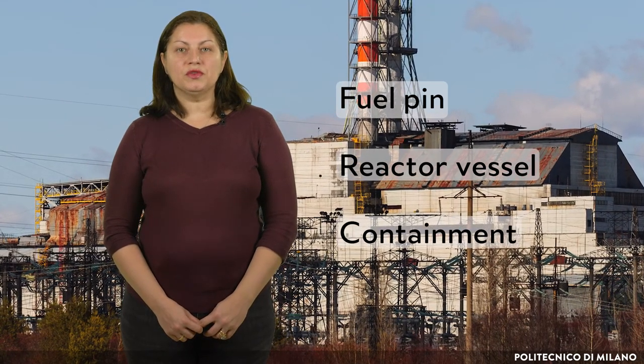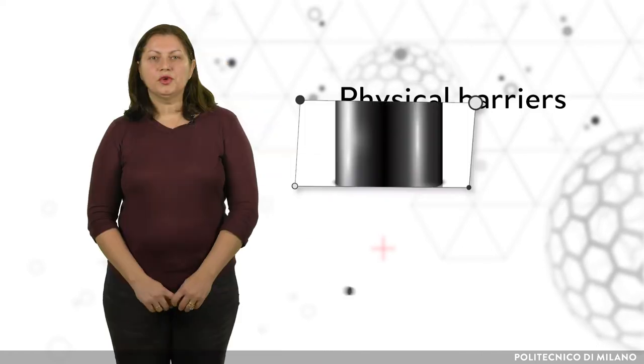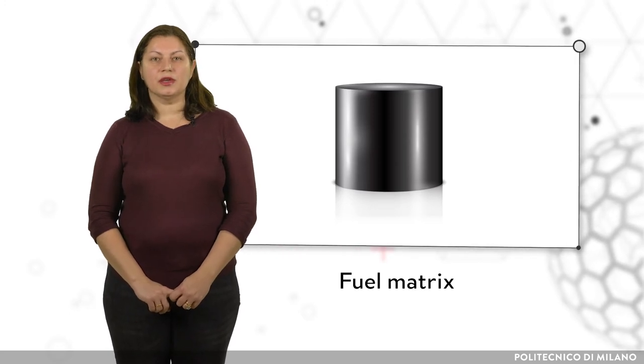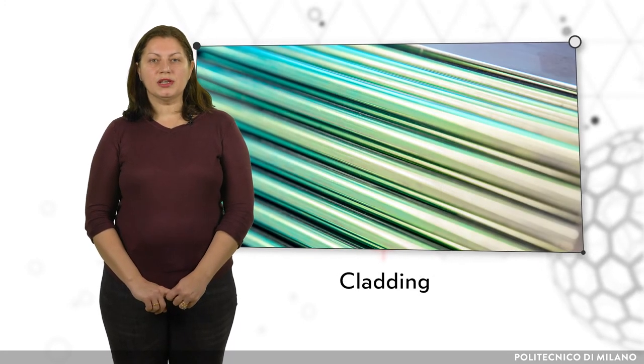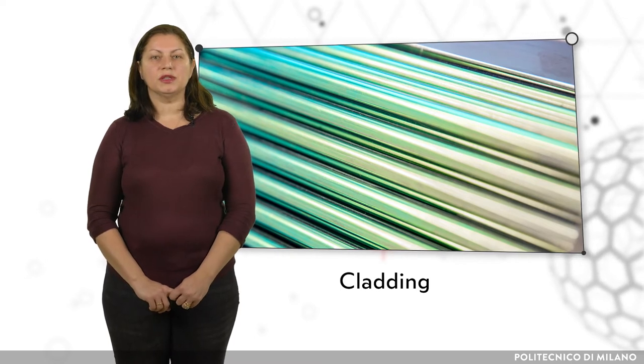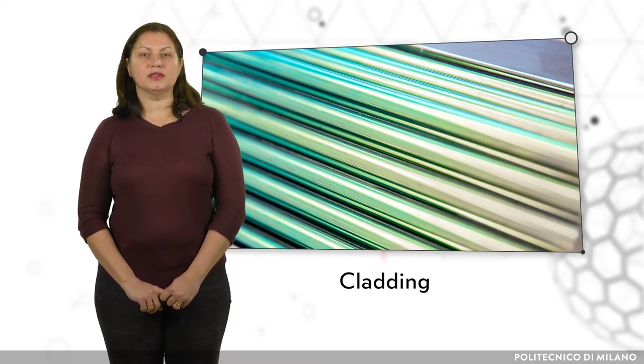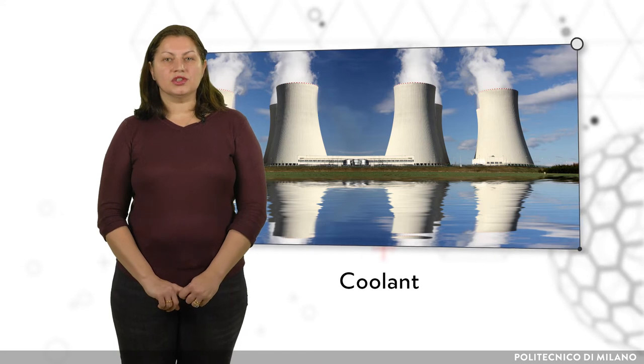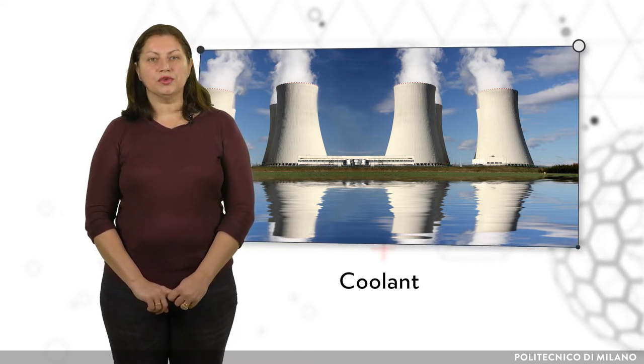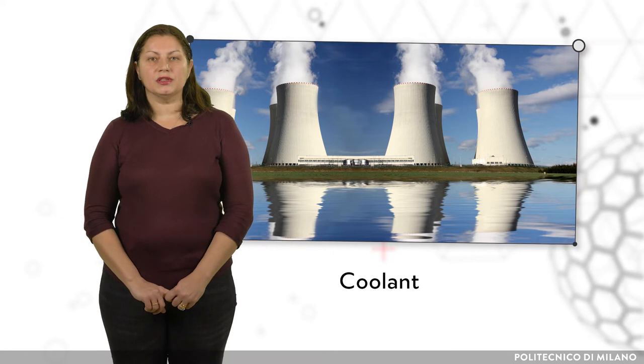There are also safety systems which prevent overheating of the core when normal cooling is lost. The physical barriers for containing radioactive material during normal operation of nuclear power plants are: the fuel matrix itself, which in many cases are oxides that are usually chemically inert, pressed in pellets with a controlled porosity; the cladding, which is made from a material that has to appear more or less transparent to the neutrons needed to start and maintain the nuclear reaction in the fuel, thus not interfering with the process, while also being sufficiently resistant to radiation and mechanical damage. The coolant has to be a medium which can easily transport heat, assuring good cooling of the nuclear fuel, and in the case of any radioactive release, it acts as a barrier by retaining at least for some time the released radionuclides.